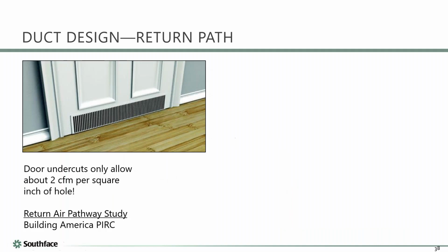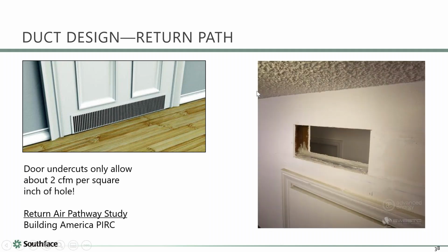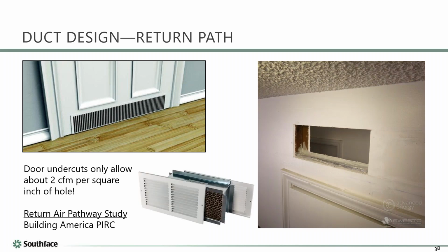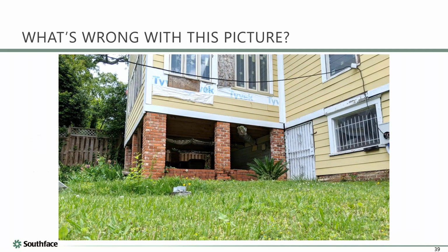We also talked about options like an undercut, and my rule of thumb is you need about 1 square inch of opening for every CFM you put in. We never seem to have enough with just a regular undercut. Did you just use a rule of thumb, Mike? I did, but some rules of thumb are not so bad. I'm just saying that we're really trying to minimize the pressure drop between the bedroom and the hallway, for example, if the door is closed. So yeah. Okay, Joey, I love this picture.